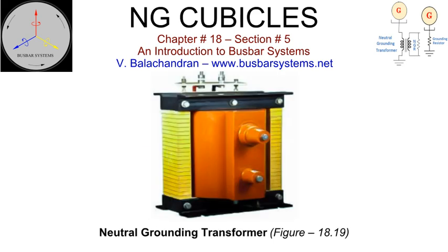Neutral grounding transformer. The neutral grounding transformers are of dry type. The rated primary voltage of the transformer should be the line to neutral voltage of the generator. However, the maximum operating flux density should be such that it has a voltage factor of approximately 2 to cater to the maximum transient overvoltage of the first cycle during the short circuit. At the rated primary voltage, the operating flux density will be close to 1.0 Tesla. This will ensure that the grounding transformer does not saturate. The neutral grounding transformers are short time rated for 10 minutes. The secondary voltage is rated at 240 volts. This will depend upon the sensitivity of the connected relay.